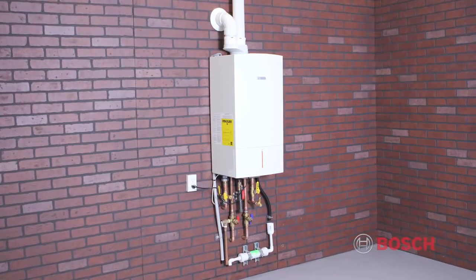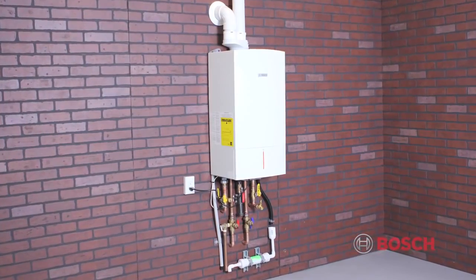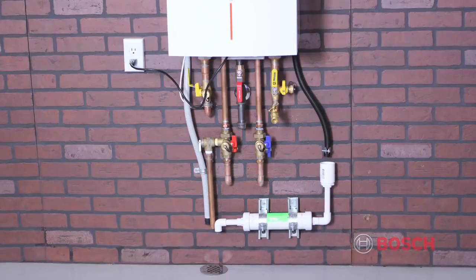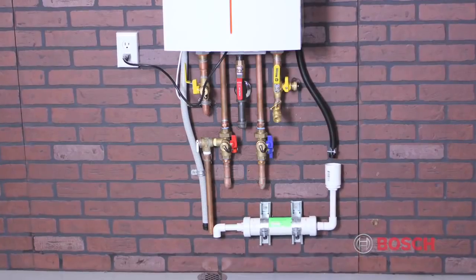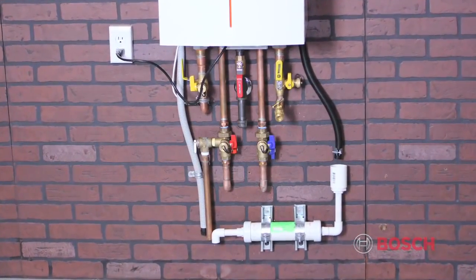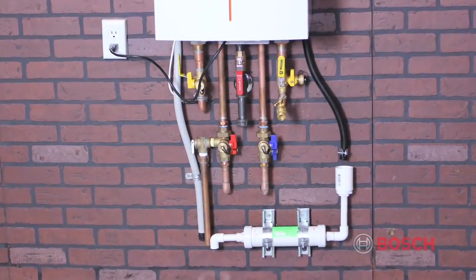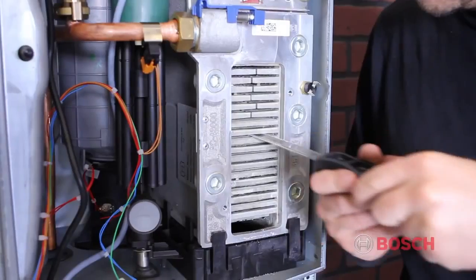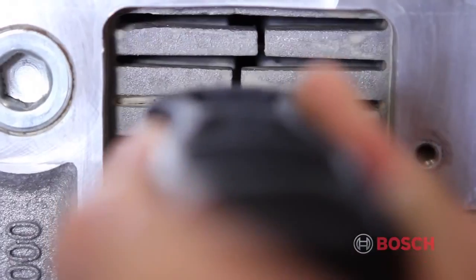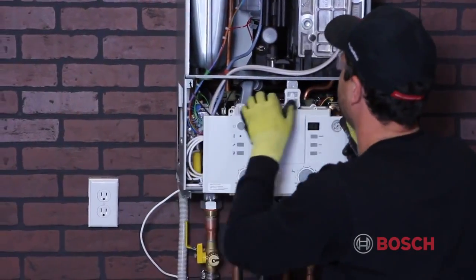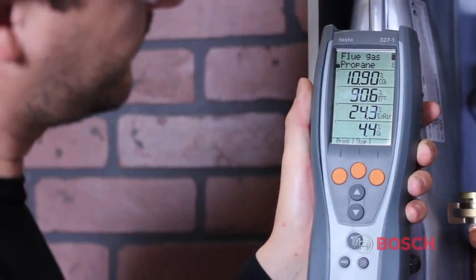The Greenstar has a very simple maintenance protocol. An annual inspection is strongly recommended. A thorough visual, safety, and combustion test should be completed prior to the start of each heating season. A physical cleaning of the heat exchanger may be required every 5 years. This is something that can be easily determined by a visual inspection and a combustion test.